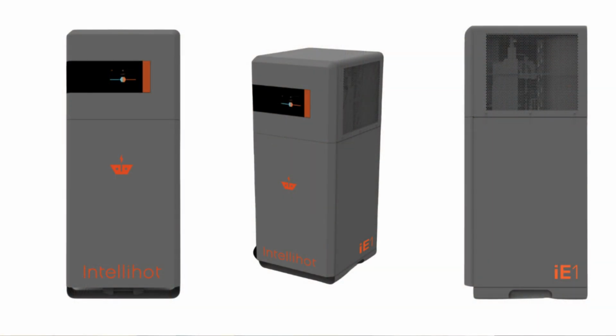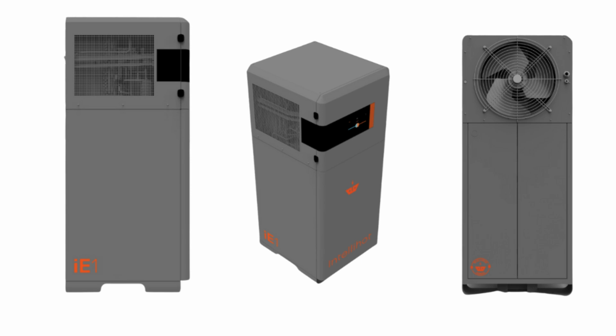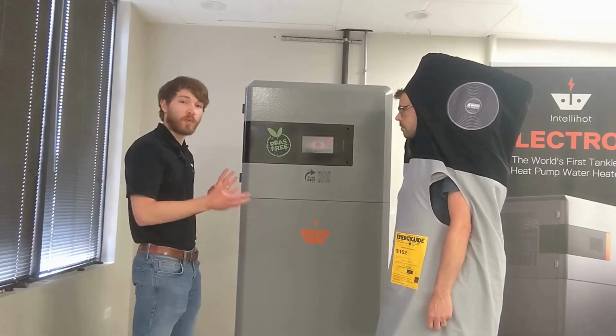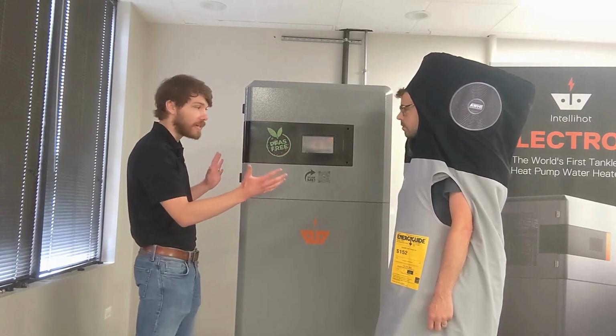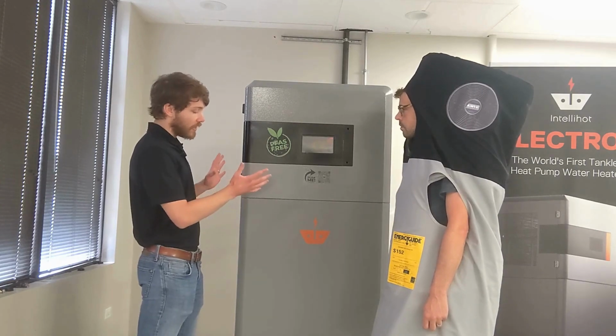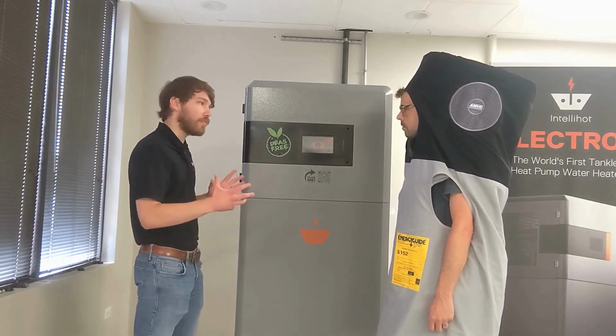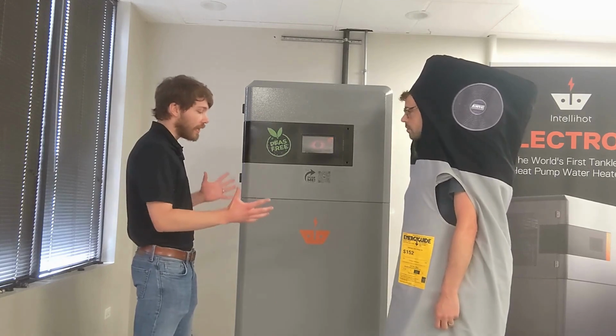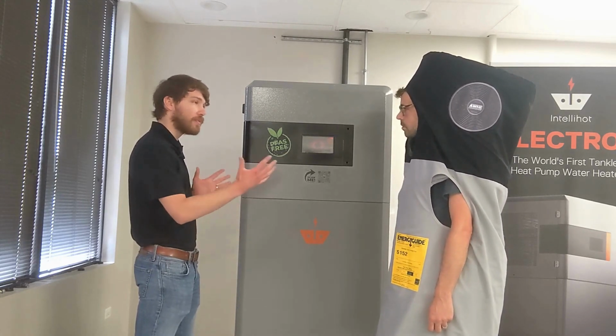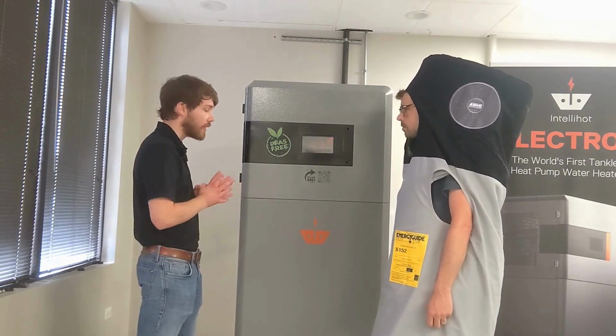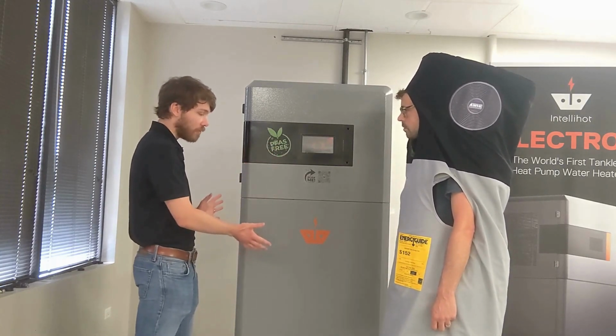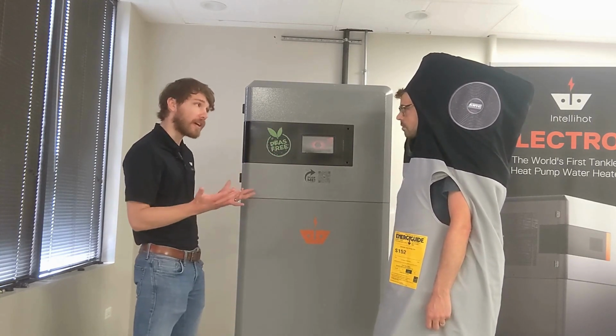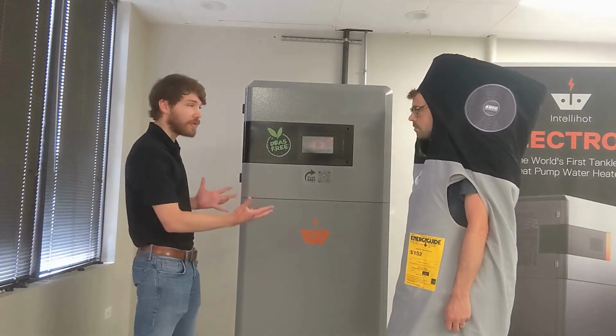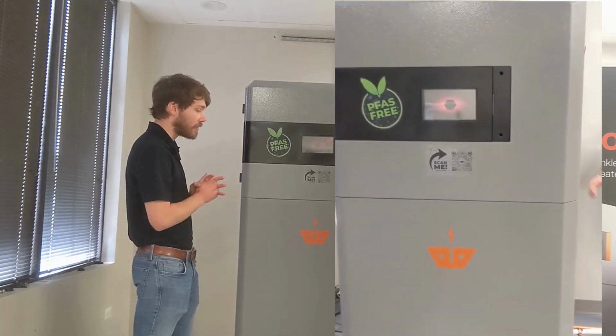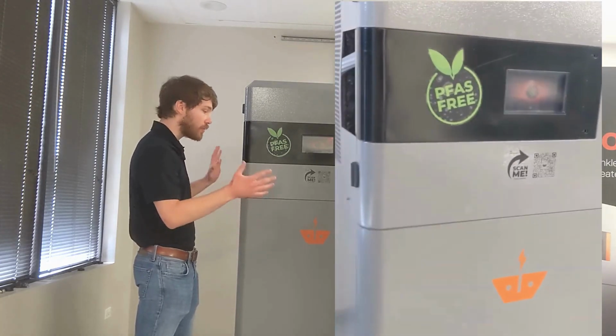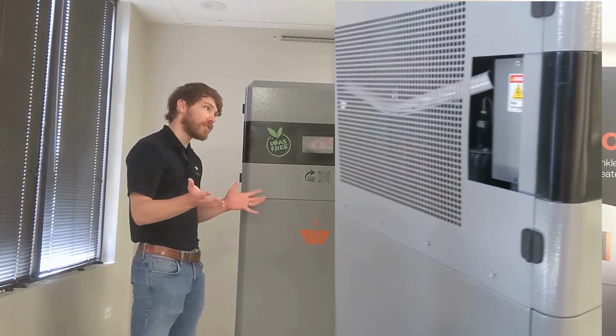We know heat pumps are very efficient, but they tend to be slow on recovery rate. So rather than storing potable water in a large series of stratified tanks, we said, what if we store a bunch of thermal energy inside what we're calling a thermal battery? Then I could grab heat from the thermal battery as needed with a potable water heat exchanger sitting on the inside. The heat pump charges up this thermal battery, which is a water and propylene glycol mix that lets us get really high temperatures and pack as many BTUs in as possible. Our potable water heat exchanger grabs that heat on demand, just like a traditional tankless system does.